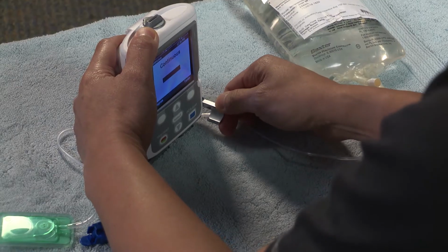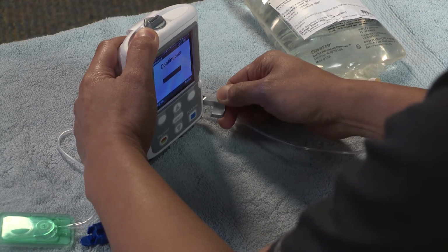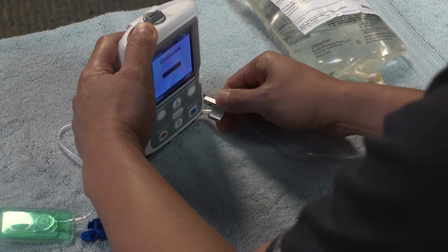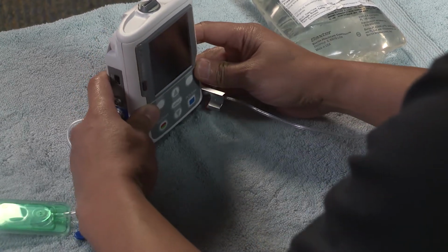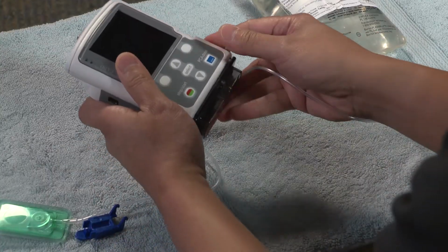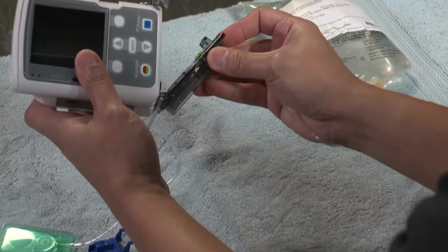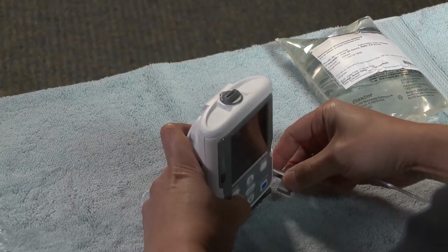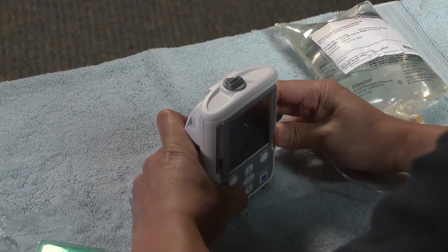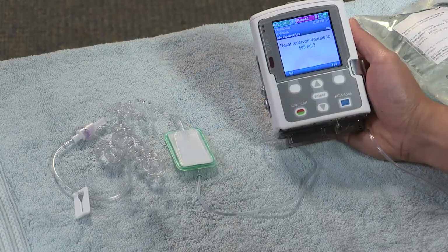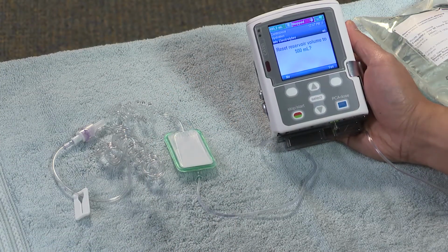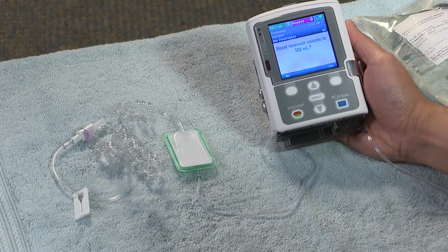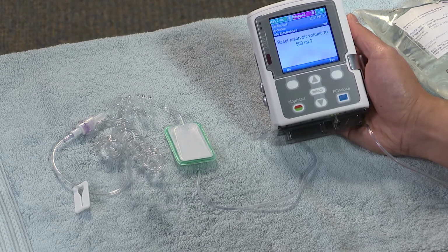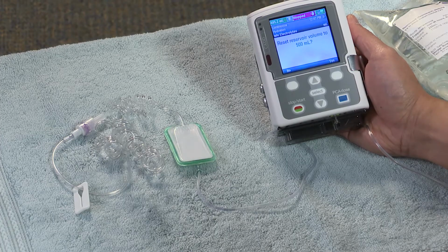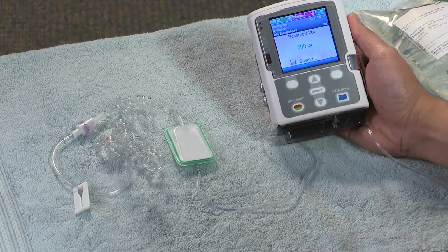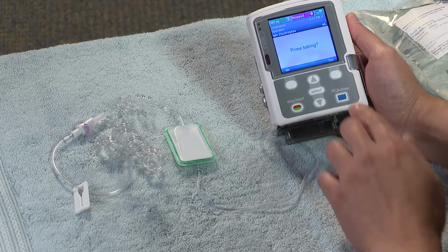If you experience resistance when lifting the cassette latch handle, do not force the latch. Remove the cassette and reattach. Turn the pump over and press down firmly. Lift the cassette latch handle into the closed position. When a cassette is attached, the pump display will show you how many milliliters were previously set by the nurse. It will prompt you to reset this volume. Press Yes. The screen will then show Prime the tubing. Press Yes.